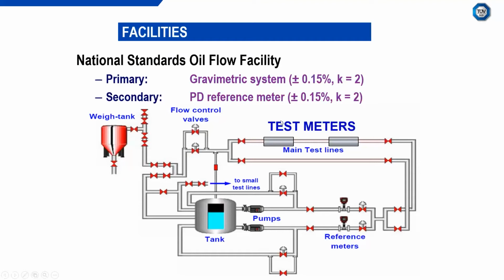Now the difference in uncertainty, why is it so much greater? It's partly due to density. With high viscosity fluids, the determination of the density is more challenging and has a larger uncertainty in our facility at present, and hence the overall uncertainty is slightly higher. We are doing work on that at present, hopefully to bring that value down further.